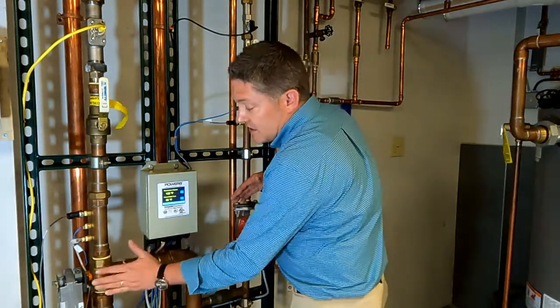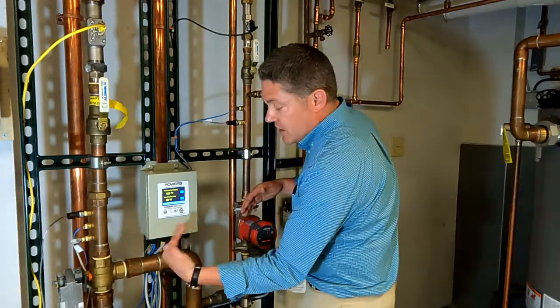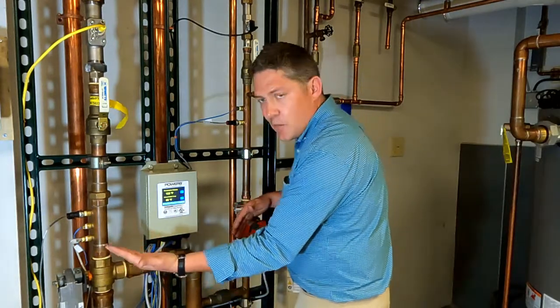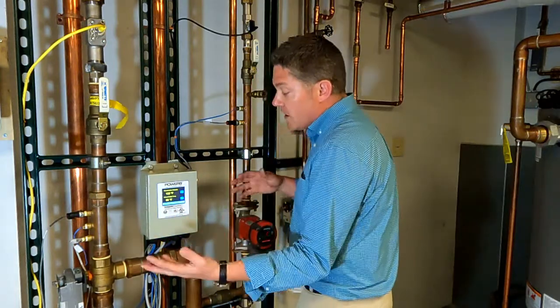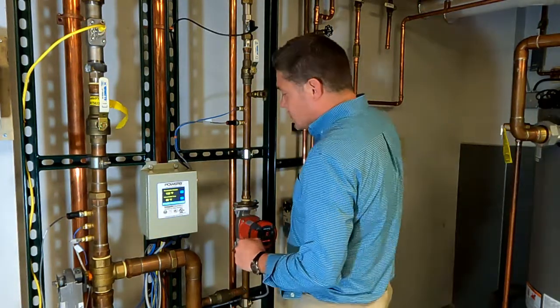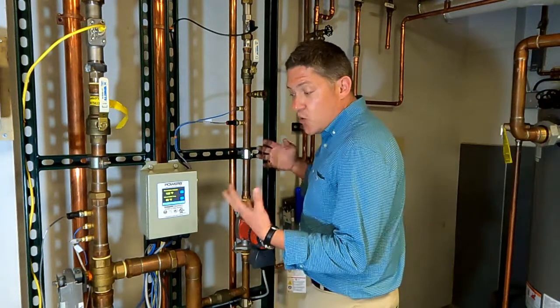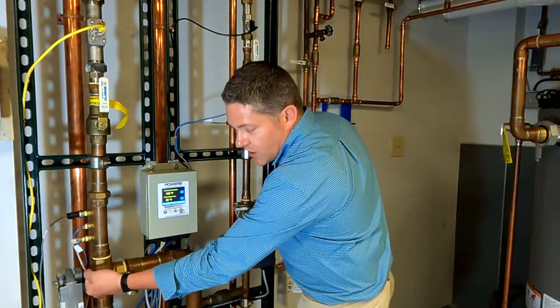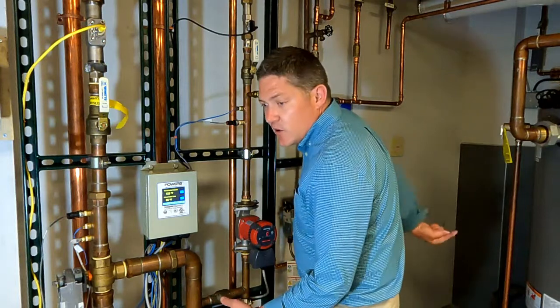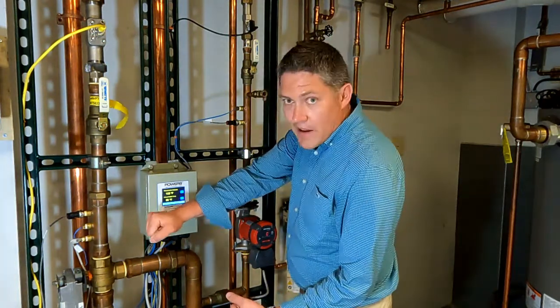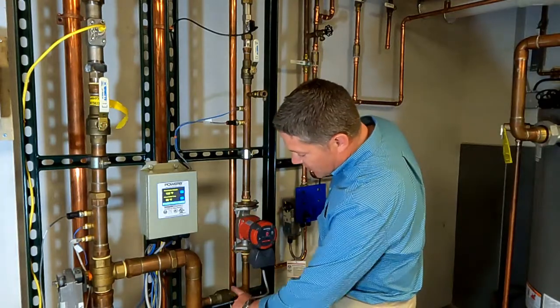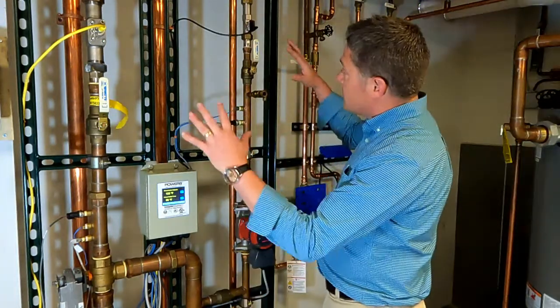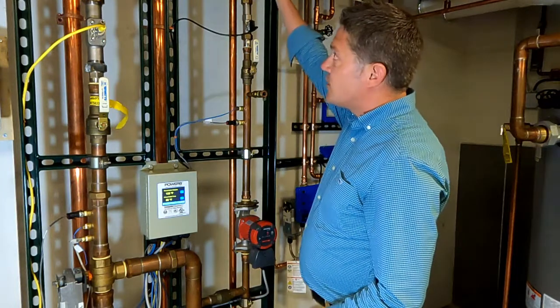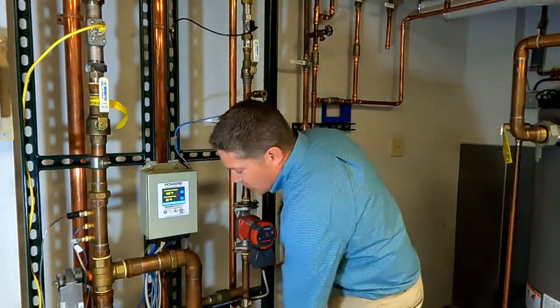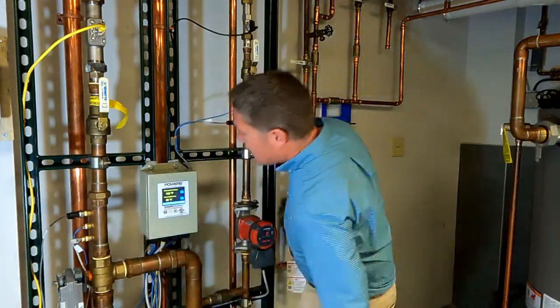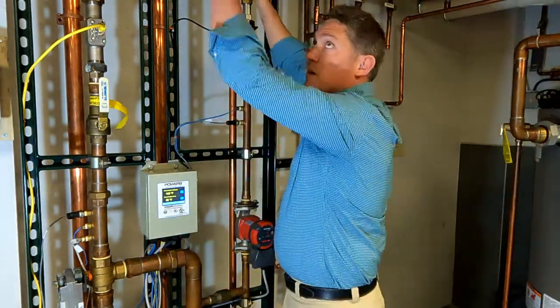So a digital mixing valve, our digital mixing valve, is able to close off about 99.9% one way or the other. So it does not need a balancing valve. It's self-balanced. So if that water comes back and it's too hot, well then it will just close off its hot inlet, which would then not allow it to travel back towards the heater, but force it all back into the cold mix outlet on this bridge right here. So this system comes on a skid, pre-piped like this. All you have to do is hook up your cold inlet, your hot inlet, and your return loop right here, and then your mixed outlet going out to the building.